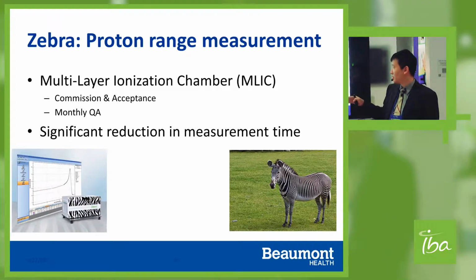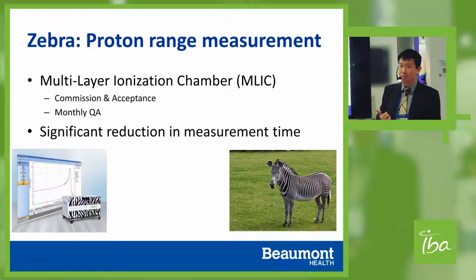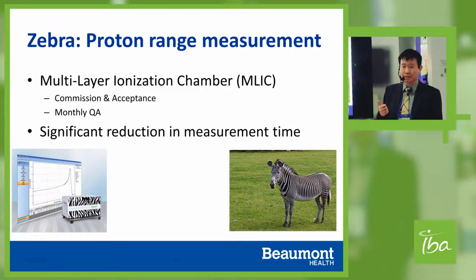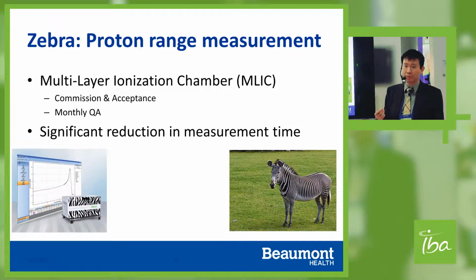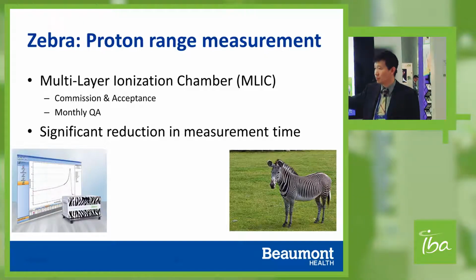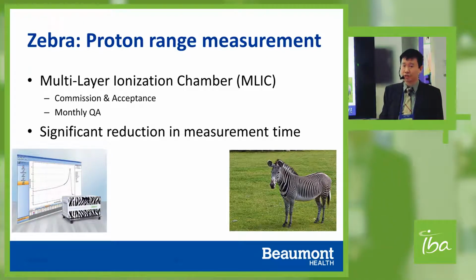So the good part is you have to measure all the immobilization devices, for example, couch, mask, alpha cradle if you use that, or you use locking system or vacuum lock. So this kind of immobilization device introduces additional range error you have to characterize before you treat the patient, and this device will help reduce significantly your commissioning time.